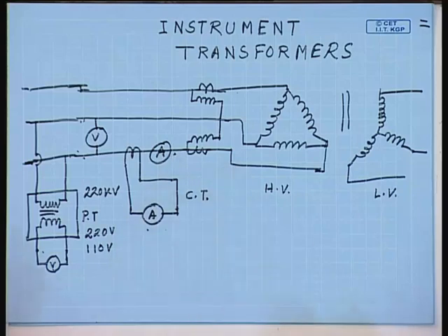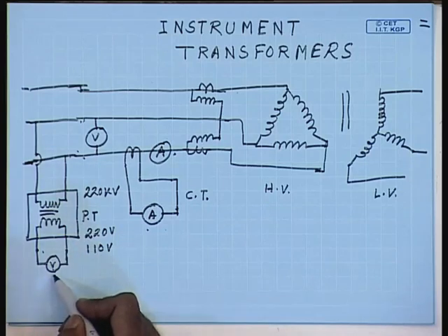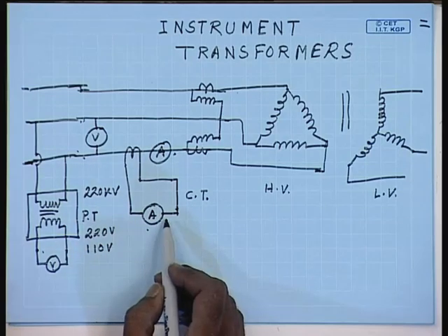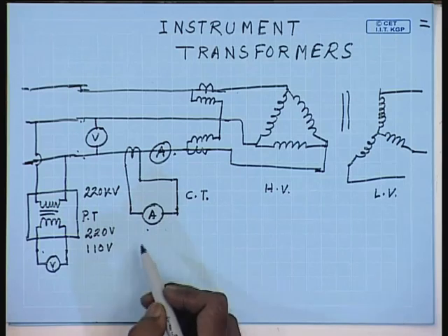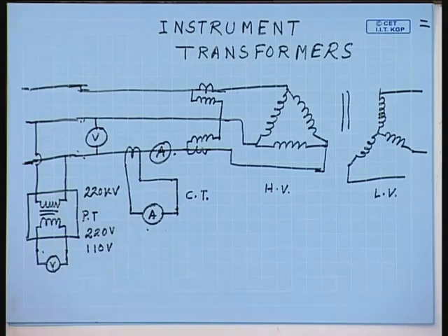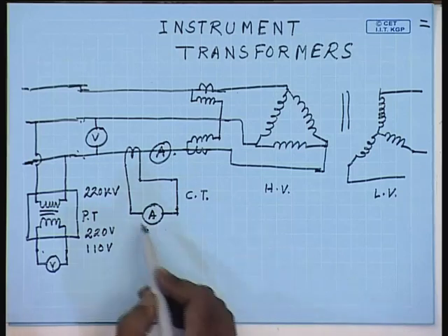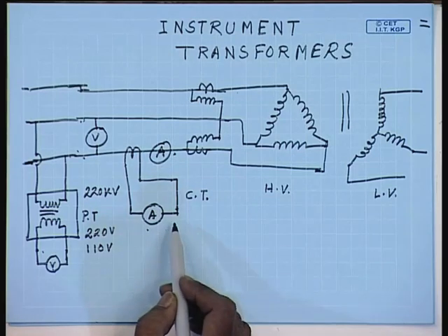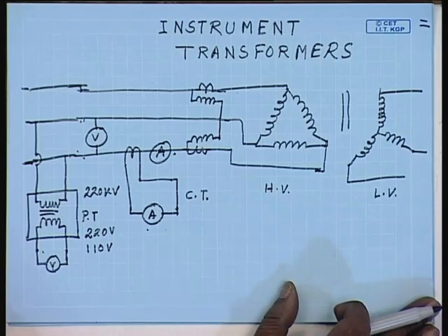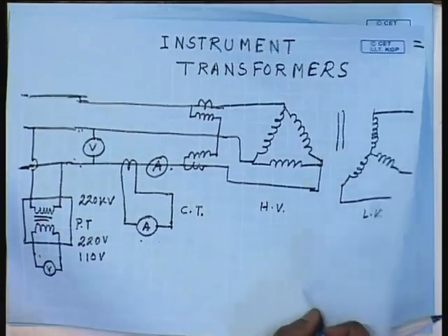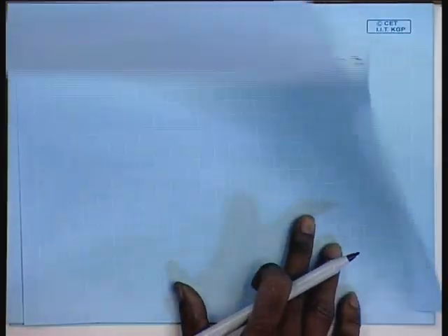Normally, these transformers will be loaded with the measuring coils of the instruments. The potential transformer will be connected to a voltmeter, whereas the current transformer will be connected to an ammeter. So, a potential transformer will work almost at no load or at very light load. Similarly, the current transformer secondary will always be almost short circuited. So, let us see what type of precaution or what type of constructional specialties are needed to make this transformer.